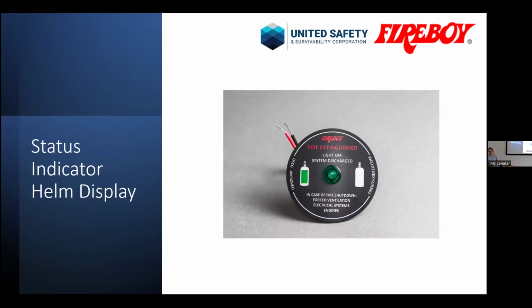There are different versions of accessories that come with the fire extinguisher. First of all, to monitor the state of it. For the diesel boats or automatic discharge, there are different versions of engine shutdowns. So every single extinguisher will come with this simple LED plate. It's the most basic visual indication. Green LED means good, you've got pressure in a cylinder. No LED means you either lost pressure or the cylinder's gone off.